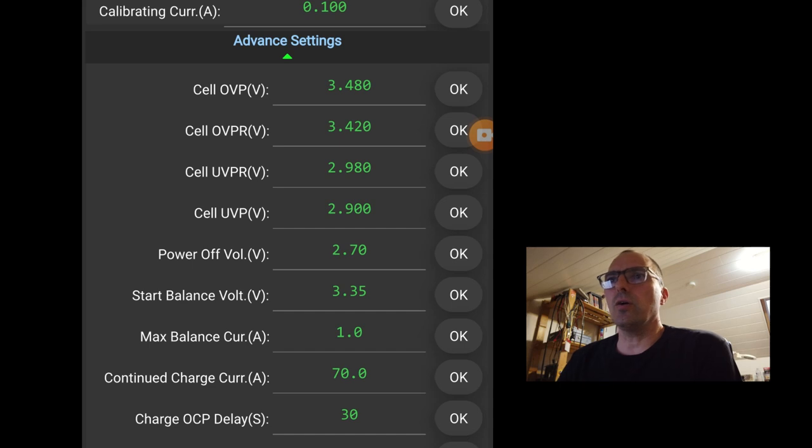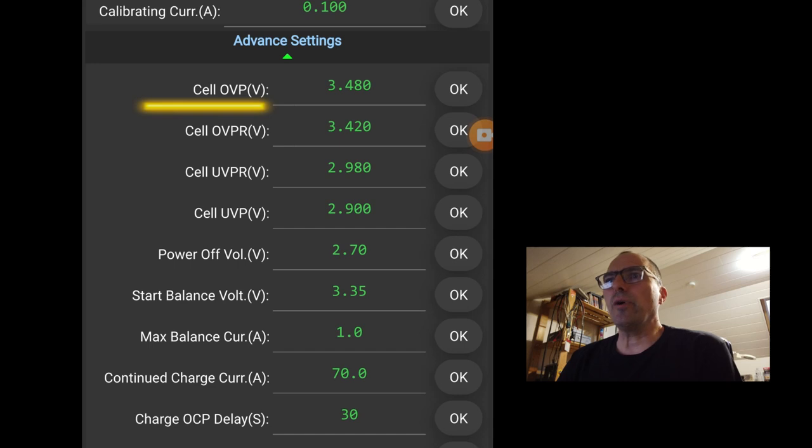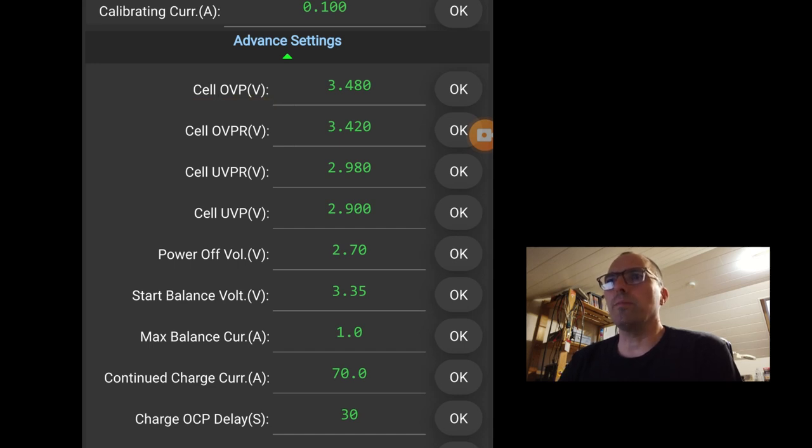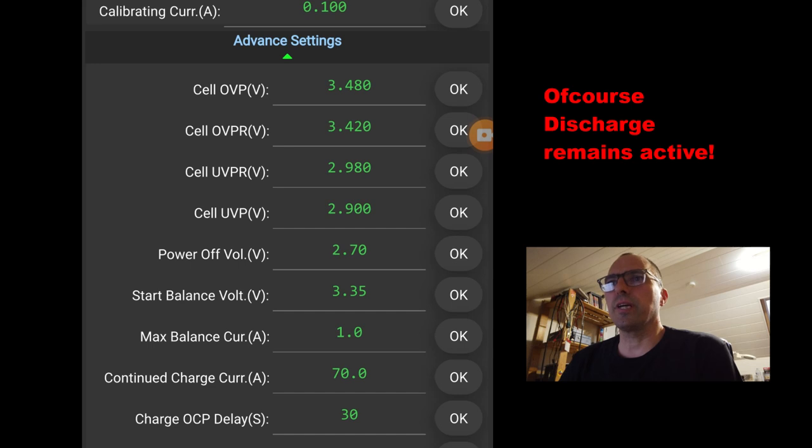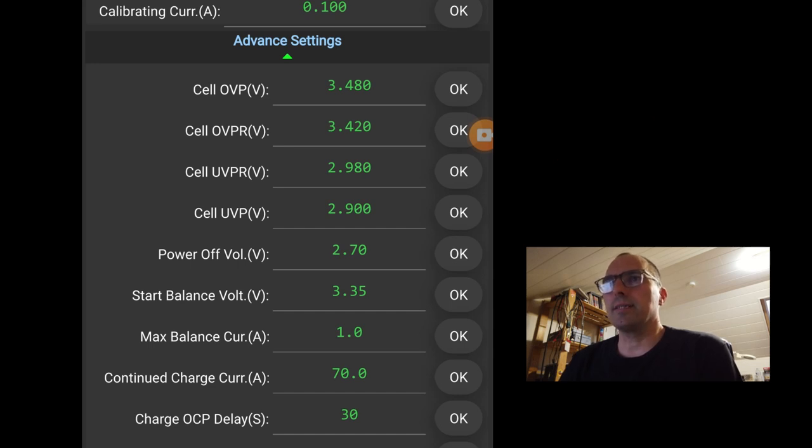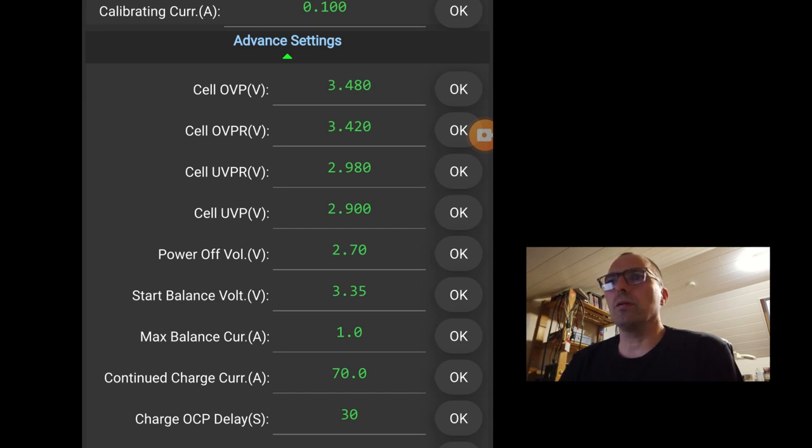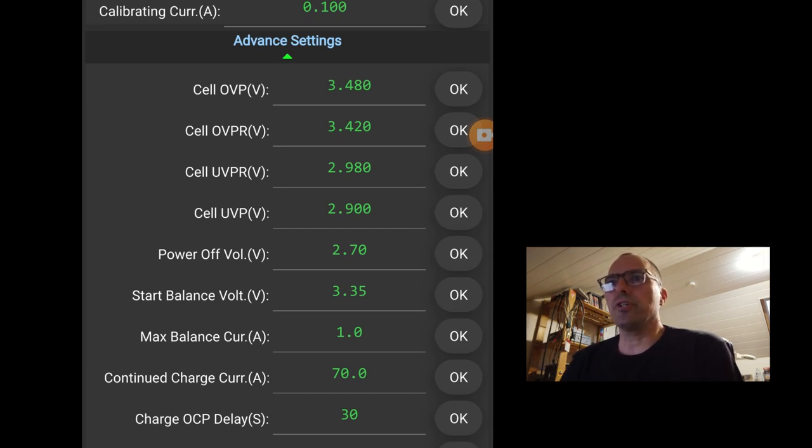So we have cell OVP, cell over voltage protection. If one of the cells hits 3.48 volt, the BMS will go in protection. The cell OVPR, over voltage protection return. When the highest cell goes below 3.42, then the BMS will unblock, will release again. Cell under voltage protection return.